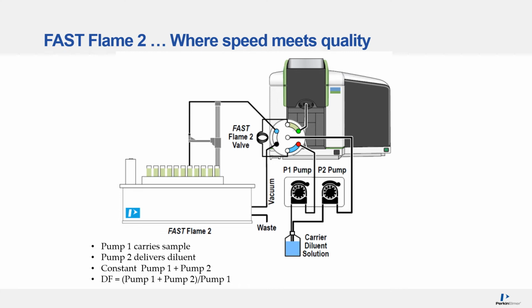And last but not least, we get to the FastFlame 2 system, for those of you that need both high throughput and auto dilution capabilities. The FastFlame 2 combines the switching valve from FastFlame 1 and the dual peristaltic pump solution from the AAPrep 2 system. So this will allow us to do both the high throughput using a vacuum pump and the switching valve, as well as having the dilution capabilities with a dual pump peristaltic pump.